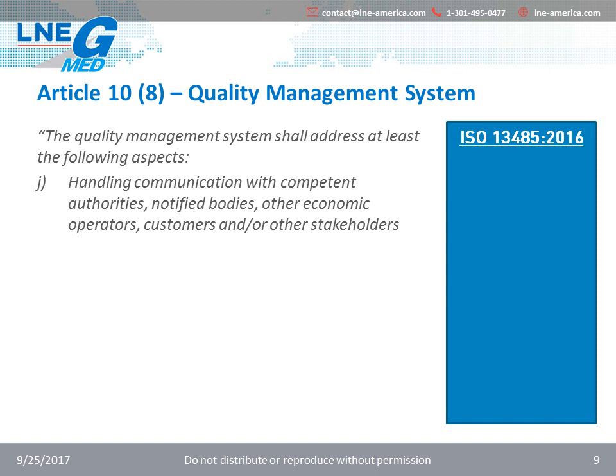The inclusion of elements related to the communication with competent authorities, notified body, and other stakeholders in the QMS is also covered in ISO 13485:2016 in section 7.2.3, which covers communication with customer-related processes, and in section 8.2.3, related to documented procedures for providing notification to competent authorities. In this case, there is not much to add other than that whatever communication is required to be done to competent authorities, to the notified body, to economic operators, importers, distributors, to customers, or any other stakeholder you may have, needs to have documented procedures in respect to your QMS, but also to the regulation of the European IVDR.